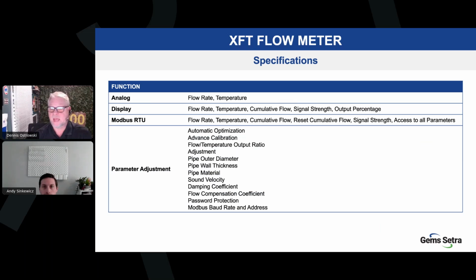Okay, next slide. Okay, the analog output, the real time, is flow rate and temperature. The display can show, as we've shown before, flow rate, temperature, and cumulative flow. You've got the signal strength in the upper right corner and the output percentage, which is directly related to the 4 to 20 output. Via Modbus, via that communication protocol, you have more ability: cumulative flow can actually be sent in real time, and also all of the parameters for programming, including advanced calibration settings, can be done via the communication protocol as well.